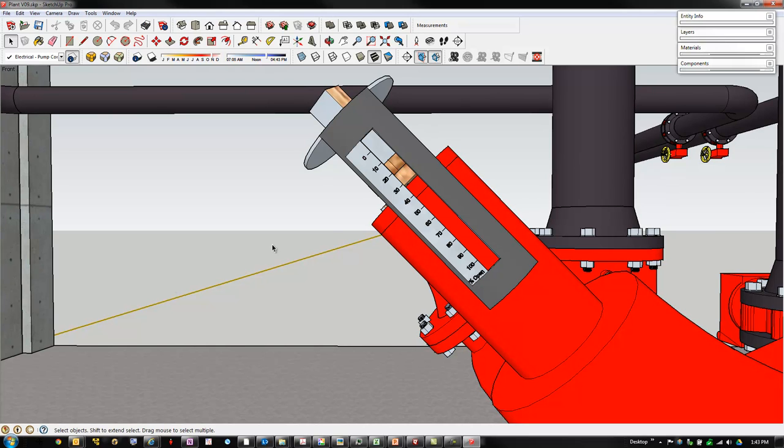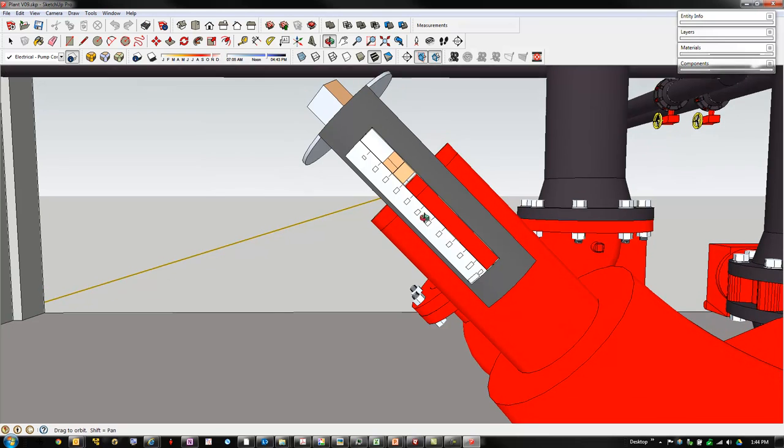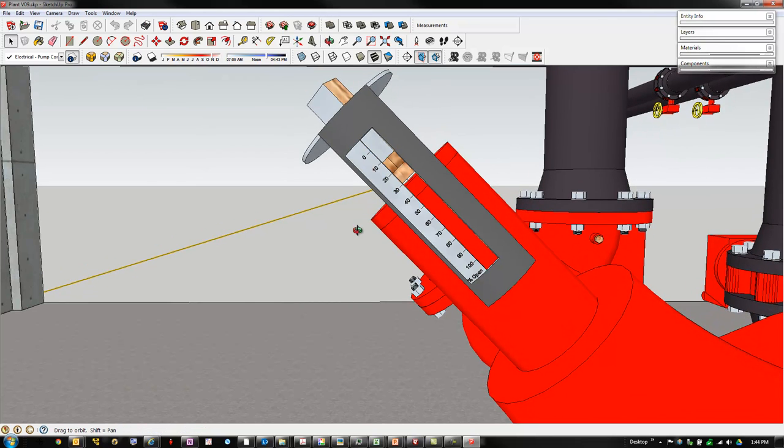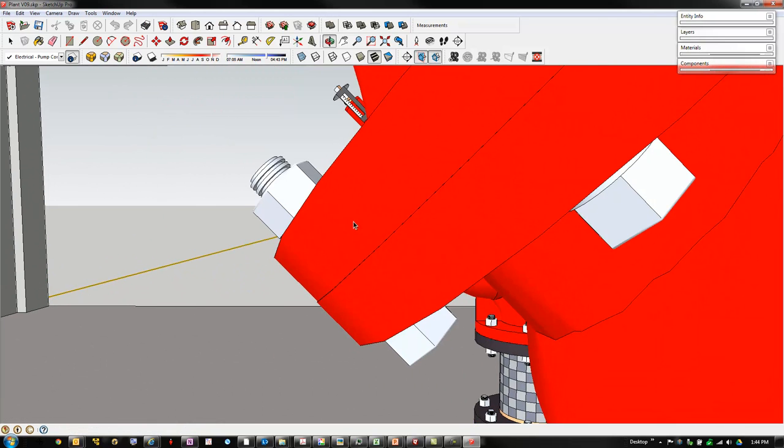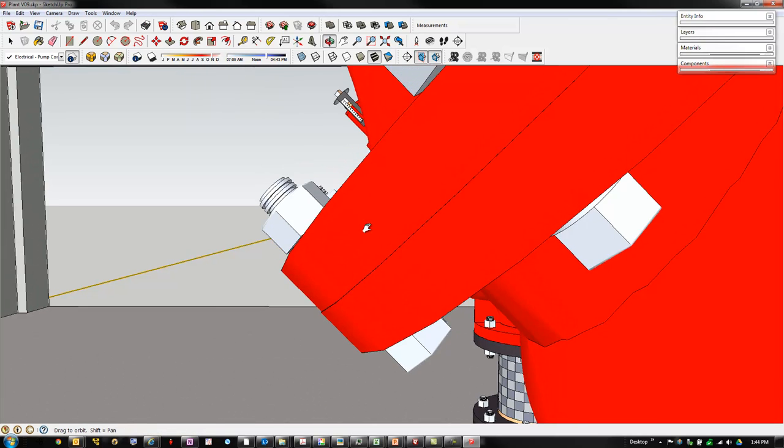Specifically, if you look at this triple duty valve, this is the calibrated scale that tells you how far open it is. And for this particular manufacturer, you read where the parting surface is against the scale. And there's perspective, so if you move your head around, that's how you'd read that. Oops, got a little close there. Excuse me.